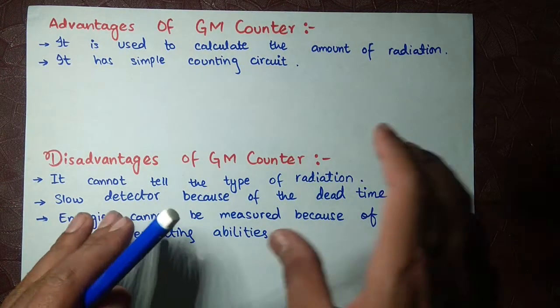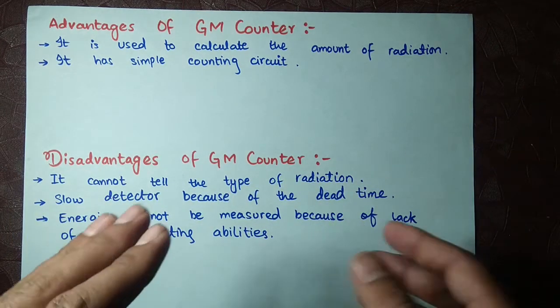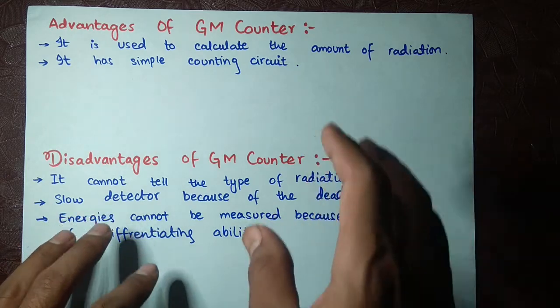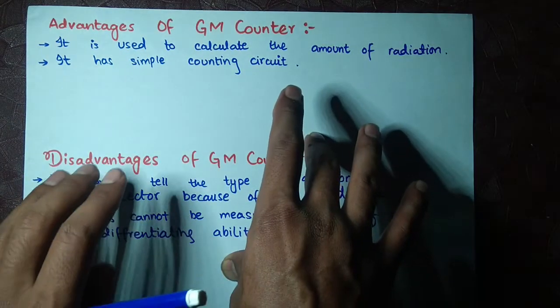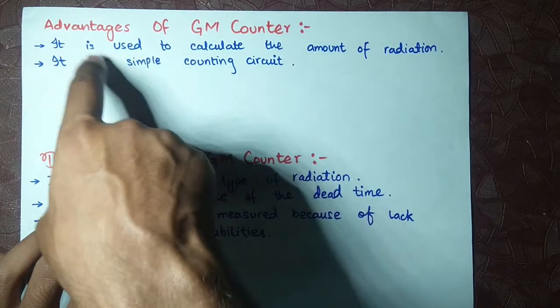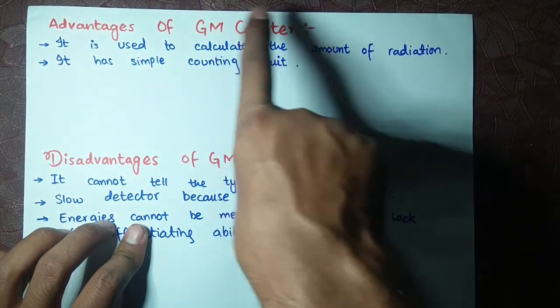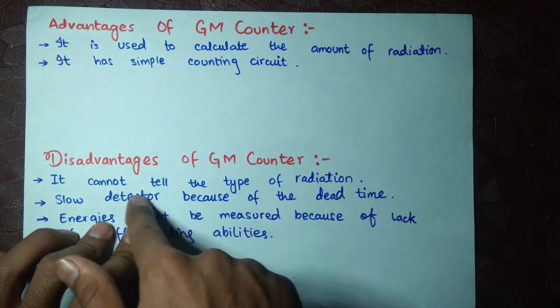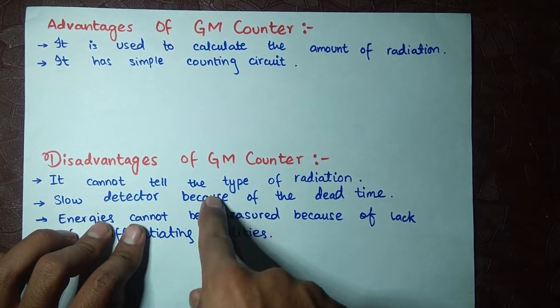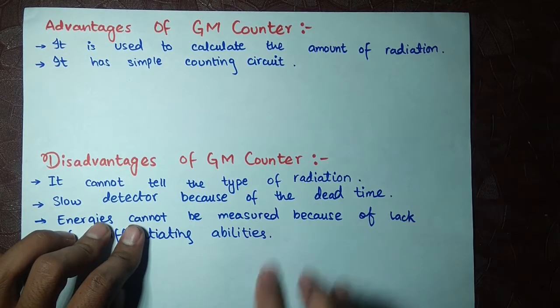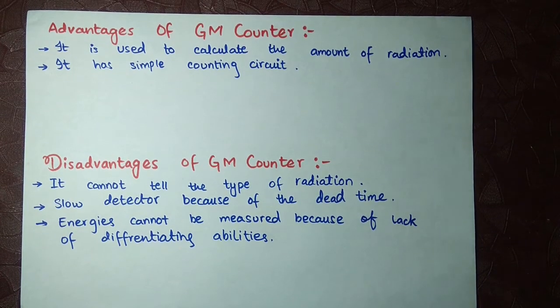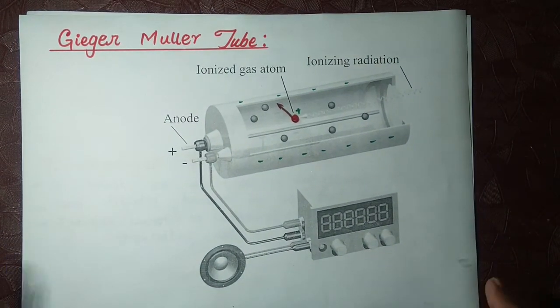Now we will talk about the advantages and disadvantages of the GM counter. I will tell you the main ones. The first advantage is that it is used to calculate the amount of radiation. However, it cannot tell or calculate the type of radiation — it only tells the amount.